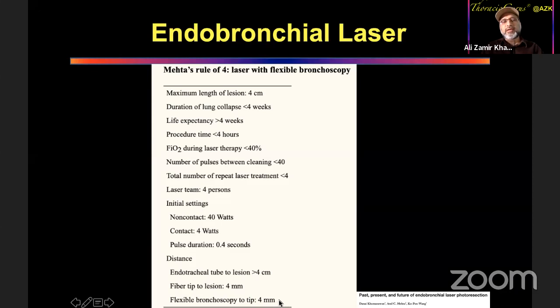The same point I'm making here is that please do not keep the fiber tip close to the bronchoscope. You'll burn the bronchoscope. So pull the bronchoscope back. At least the minimum distance is 4 millimeters. In fact, most of us keep it at a centimeter away or 2 centimeters away, because the last thing I want is the laser to reflect back on the bronchoscope and burn the bronchoscope.